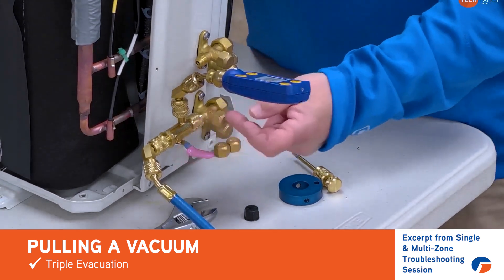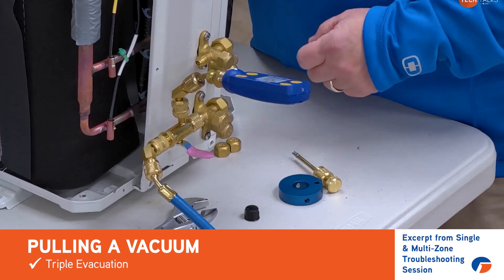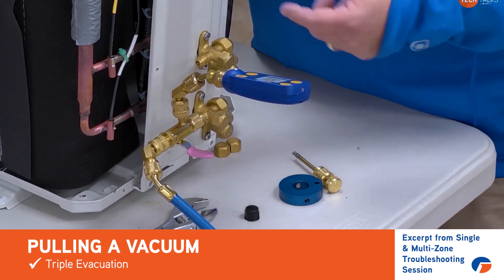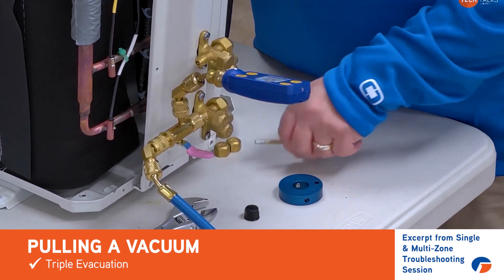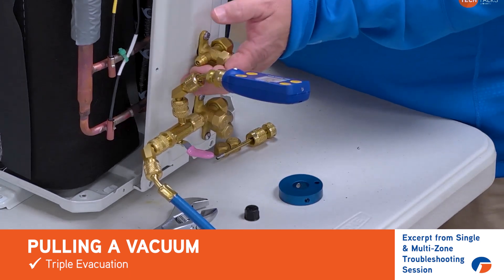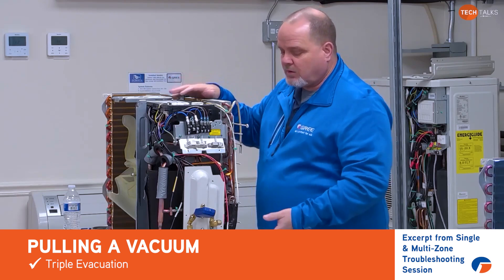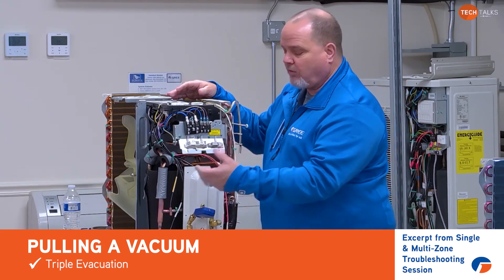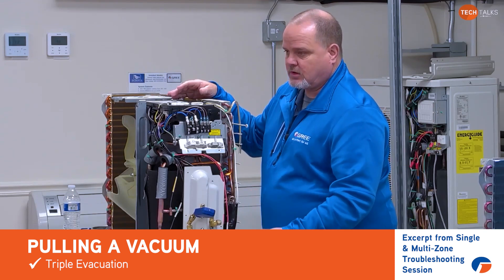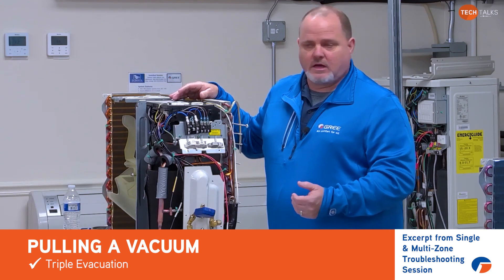By having the valve cores out, you improve your flow and you're going to decrease the evacuation time — in other words, speed it up so that we get our vacuum done even faster. When you are pulling down a vacuum for the entire machine, we highly recommend that we pull a vacuum until it stalls — in other words, we're no longer achieving any movement with the vacuum gauge.